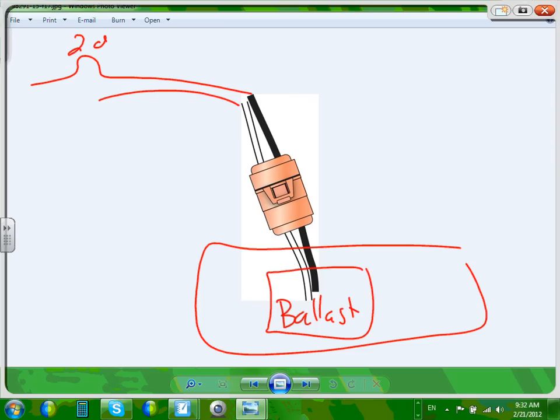So now, to change the ballast, it's really a piece of cake. These are load interrupters, you unplug them, you push right in here. When you push it, you interrupt, it's fully insulated, you open it, and now the whole fixture is dead, including the ballast. Change the ballast, and do all this stuff. This is a requirement on all fixtures that have two ends. Safety. In 2011, if you're a project manager, Phil, you also require them in retrofit. If you retrofit equipment, you have to change them. So pay attention to that disconnect for fixtures.